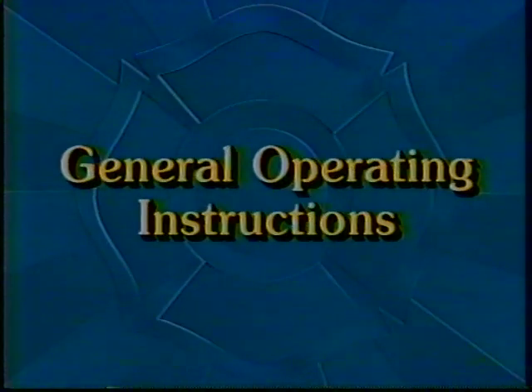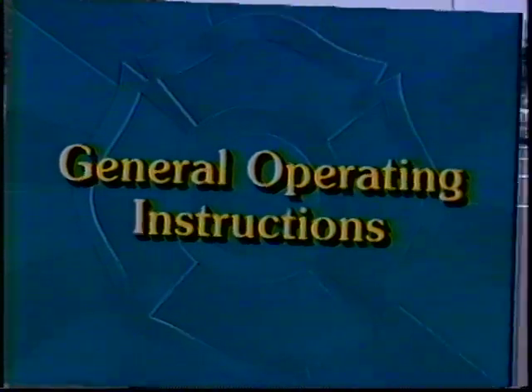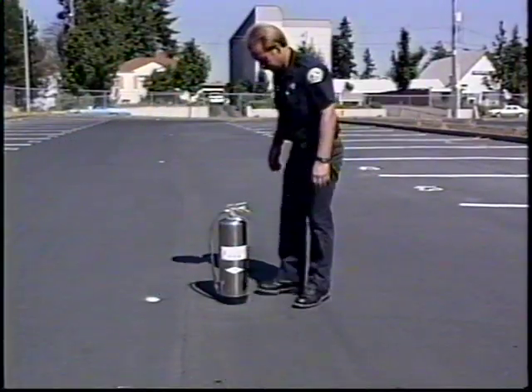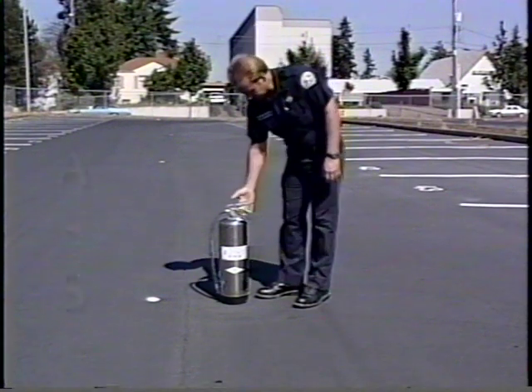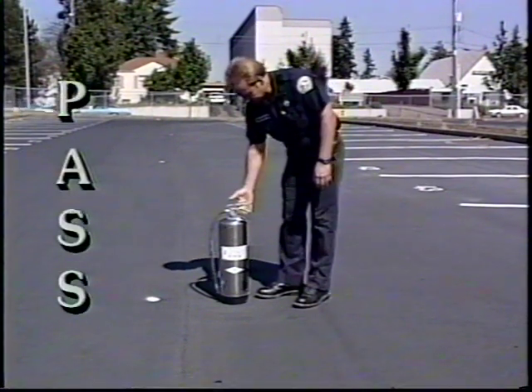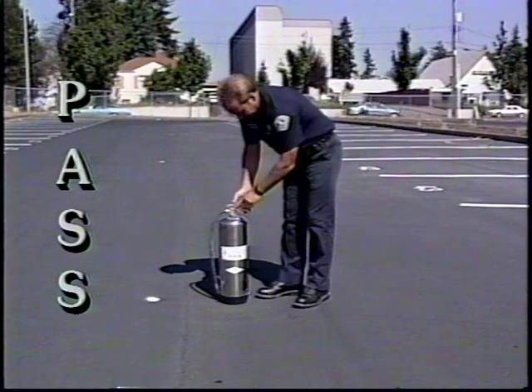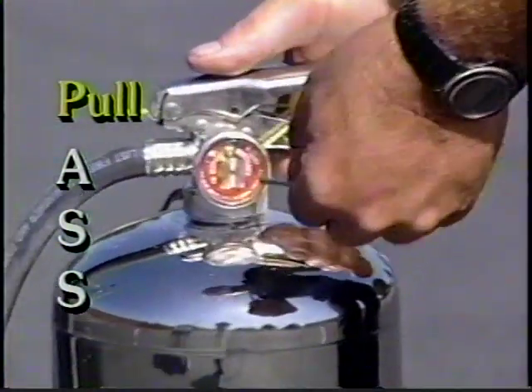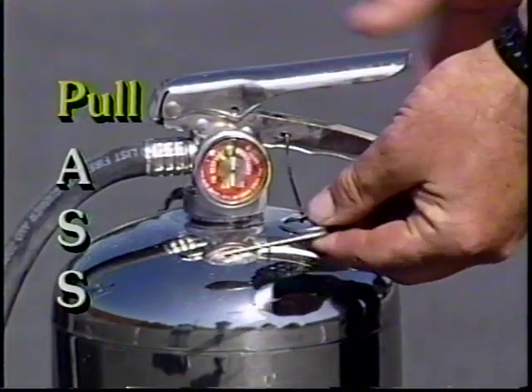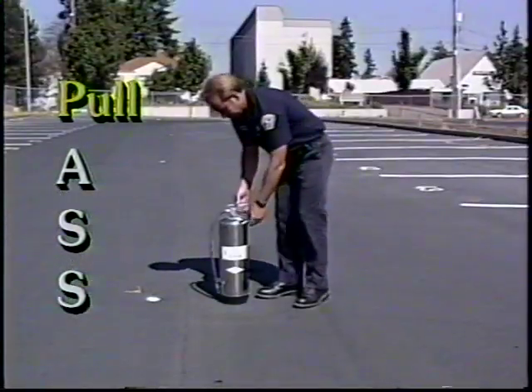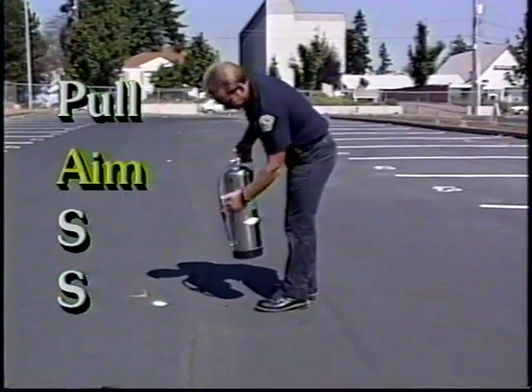Although there are different types of extinguishers for different types of fires, the general operating instructions for all handheld extinguishers are the same. General operating instructions for handheld fire extinguishers can be remembered by the letters PASS. The P stands for pull the pin at the top and break the plastic or wire band. The A stands for aim the nozzle toward the fire.